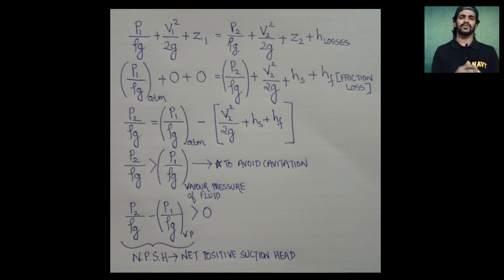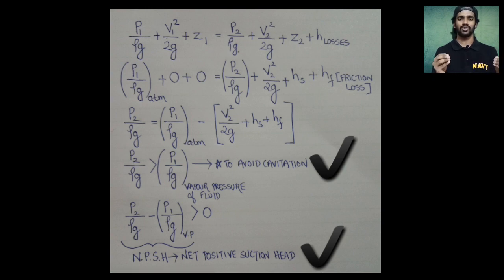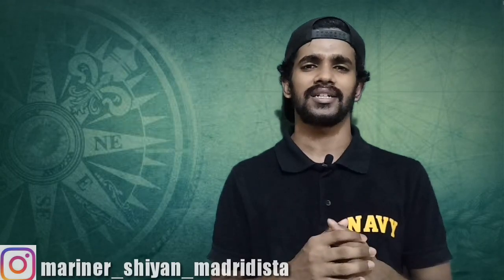To summarize: the pressure at the eye of the impeller should always be greater than the vapor pressure of the fluid — if not, cavitation will occur. NPSH is the difference between the pressure at the eye of the impeller and the vapor pressure of the fluid. We must always keep this difference greater than zero; if it becomes negative, cavitation will occur. Our main intention is to always keep this difference positive.